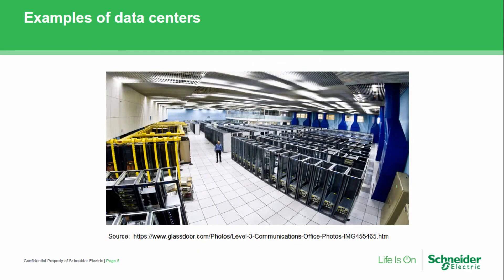Let's take a look at another data center. It's a bit bigger, and right away you'll notice two-foot-by-two-foot tiles — this is a raised floor data center. Computer room air handlers or air conditioners, shown here in blue, blow cold air into the space beneath the raised floor. Tiles with small holes allow that cold air to come up in front of the servers. The units are also ducted to the drop ceiling plenum, meaning hot air gathers up there and comes back down, indicating some kind of hot aisle containment or vents allowing hot air to reach the drop ceiling.